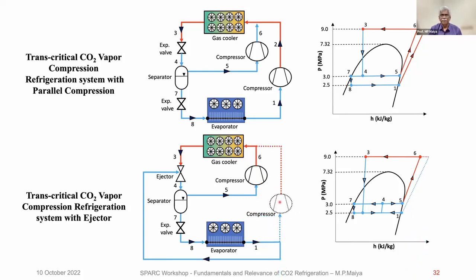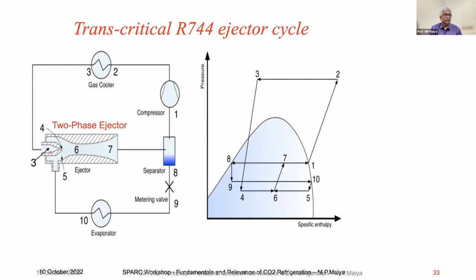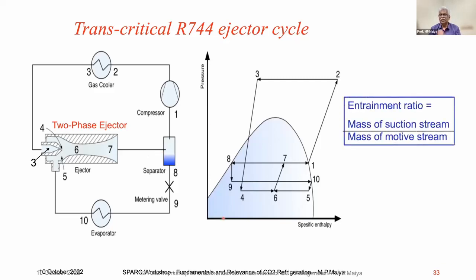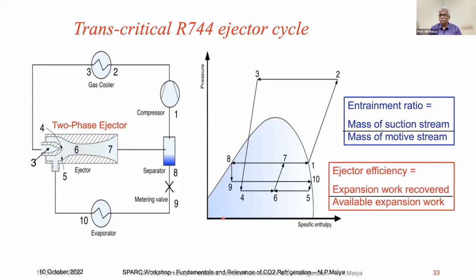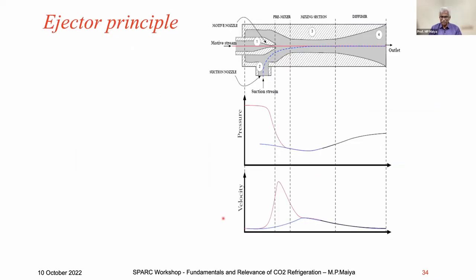So this is the ejector system, and you can see the ejector. The high pressure gas expands and becomes supersonic, okay, and it sucks in the low pressure gas, mixes, and recovers the velocity into pressure. So we have two parameters: entrainment ratio and ejector efficiency. Okay. How it works, you can see: the motive stream, the high pressure gas, its pressure decreases and velocity increases, pressure to kinetic, and then in the mixture the pressure regain takes place at the expense of velocity.